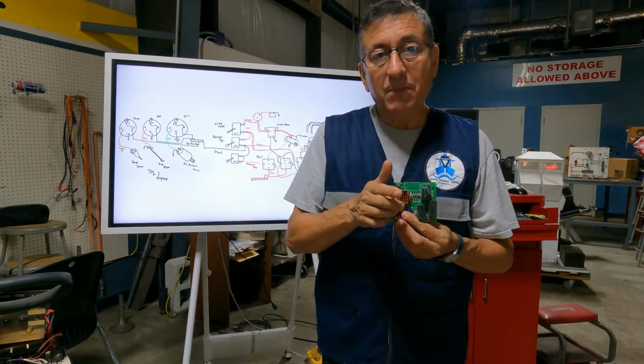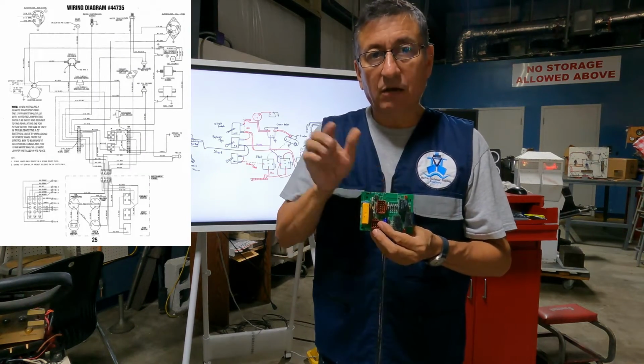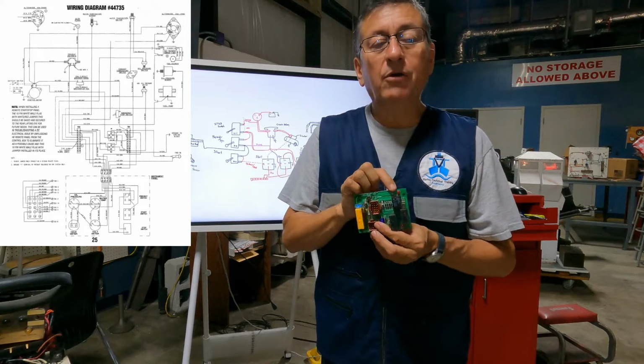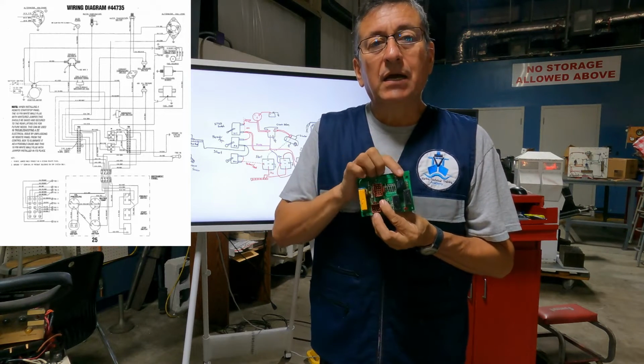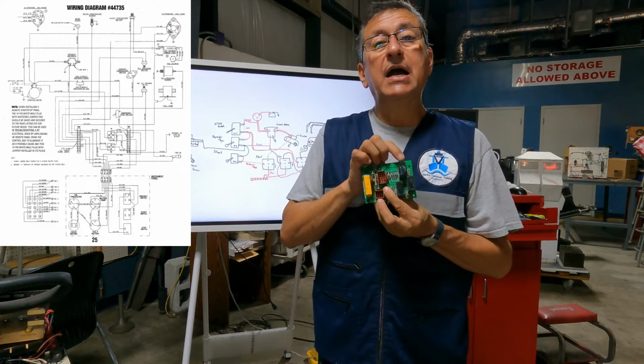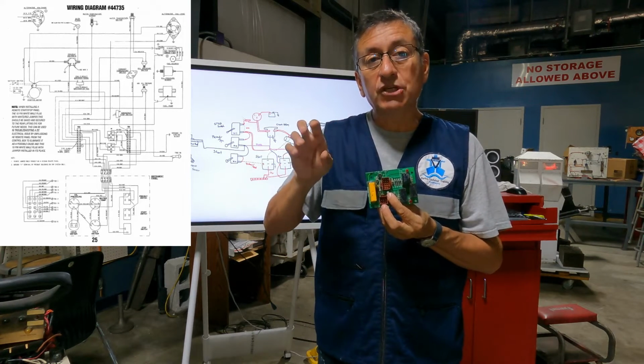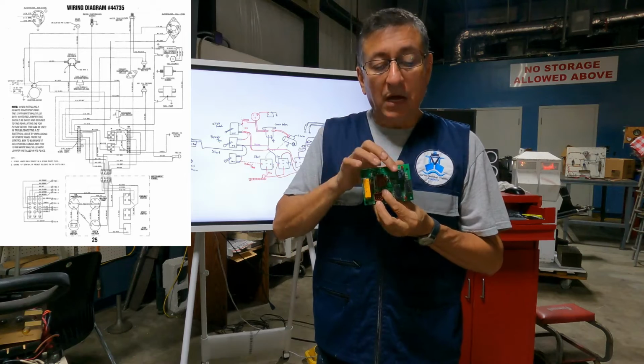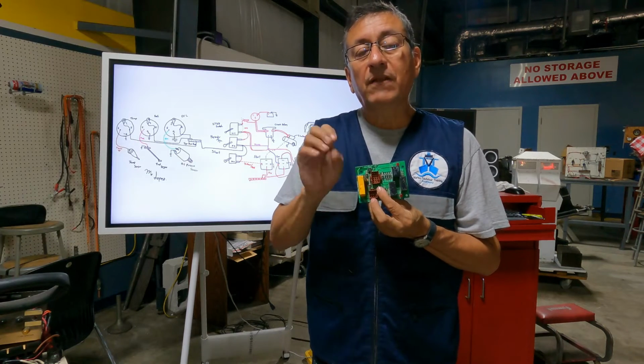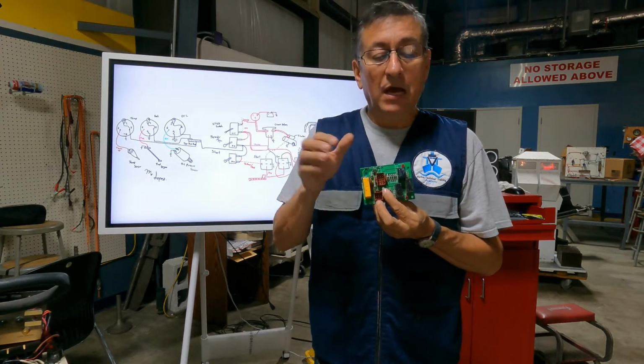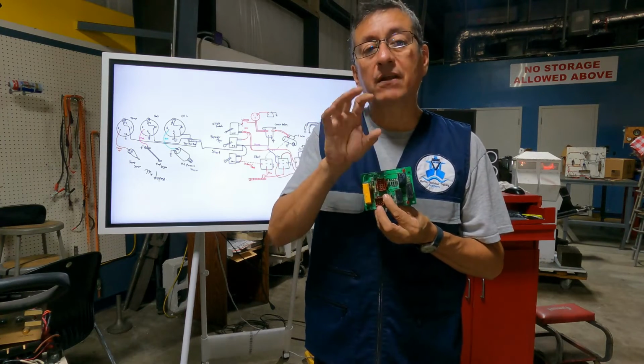Check in the manual, check the wiring diagram in the service manual, how the LED for each relay should behave. The crank relay flashes during cranking. When the engine starts, the run relay flashes, then stays solid afterward. Each LED has a different behavior.